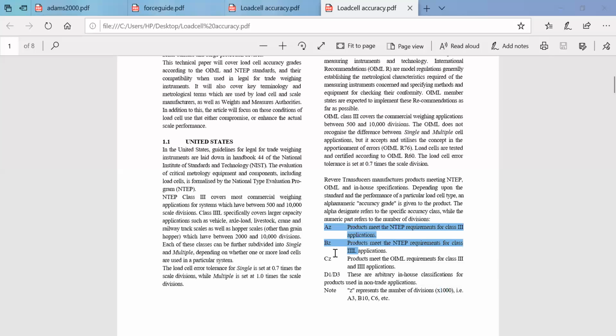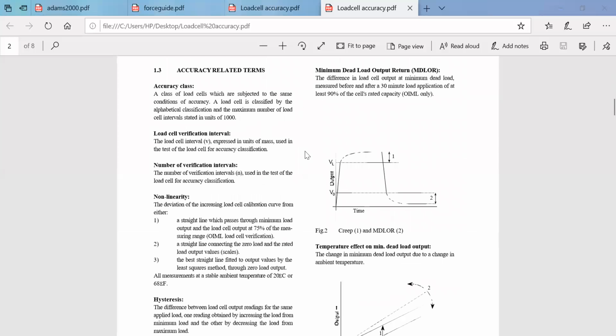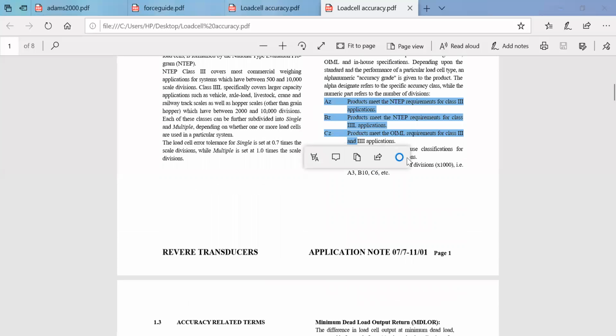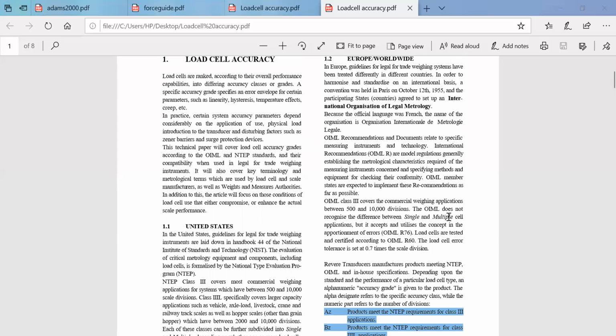We are just explaining here the protocol or the terminologies, how it will be used. So this Z stands for the scale, the number of divisions. This division can be a multiple of 100, anything into 1000. Likewise, I've told you A suffix Z. Here instead of Z we can replace it by 3, so A suffix 3 represents the number of divisions in that particular class. Similarly, instead of BZ you can write B10 or B15, depending upon the number of divisions which has been classified with respect to the accuracy level. Similarly, C6. Likewise, the numbers could be changed. This is the basic terminology the Europeans followed as per the OIML standard.